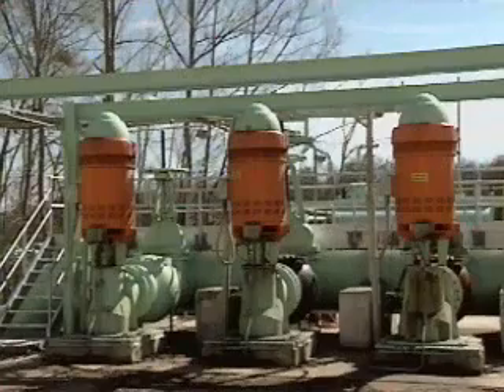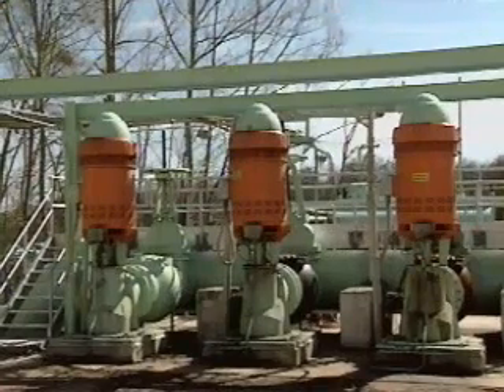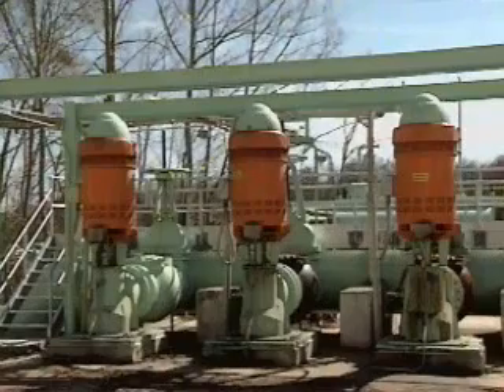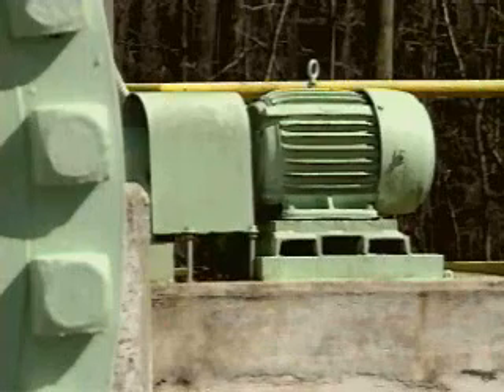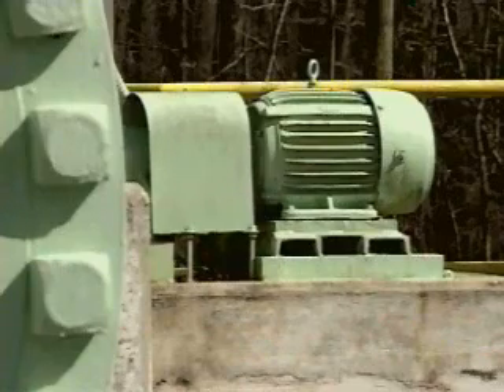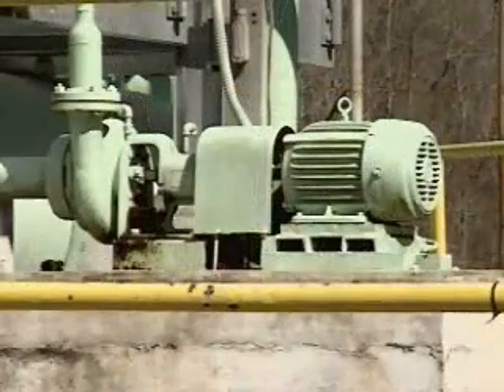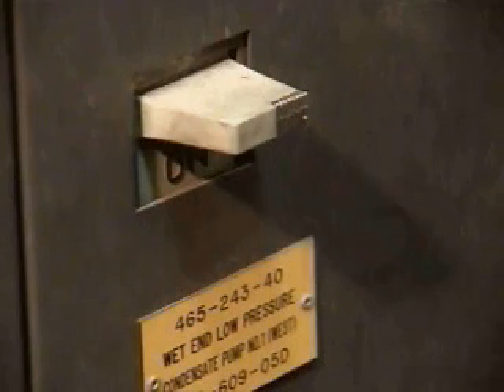Preventive motor maintenance is the easiest type of maintenance to do. The primary purpose of preventive maintenance is to maintain equipment in good operating condition. Preventive maintenance is conducted on a routine basis. Routine basis can mean daily or weekly or at any other short-term interval that is appropriate for the equipment. Preventive maintenance generally is done in the field. That is, the equipment is not removed from its location. No disassembly of the motor is required. Preventive maintenance usually does not require the equipment to be taken out of service. However, at times it may be necessary to tag out the motor from the power source. Select Next to continue.